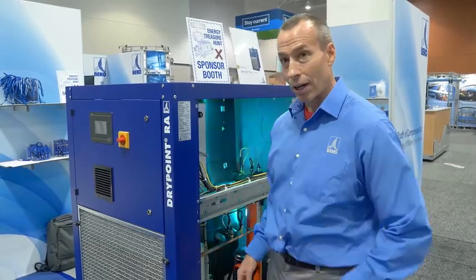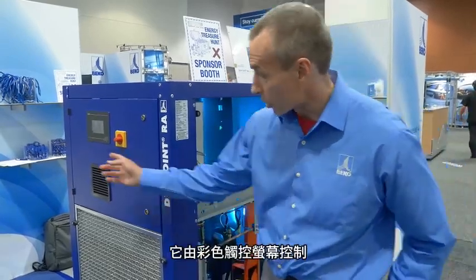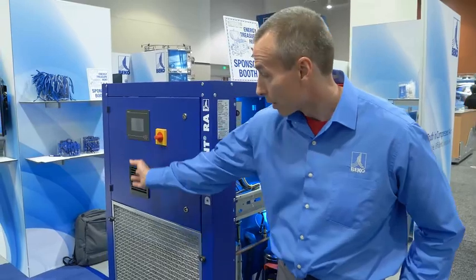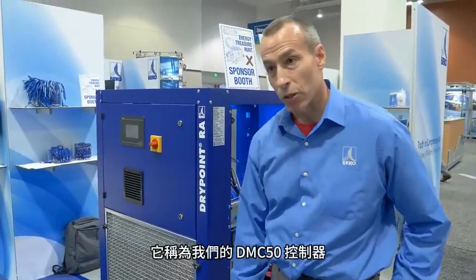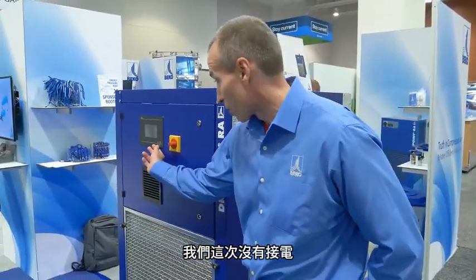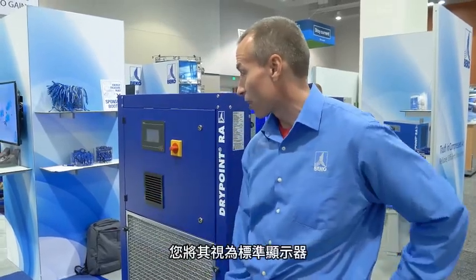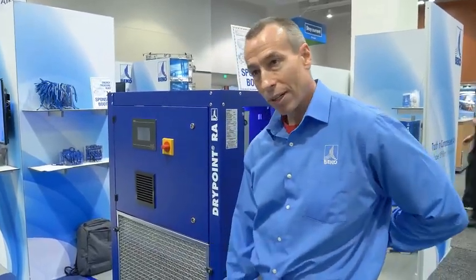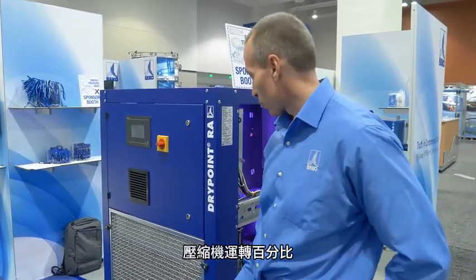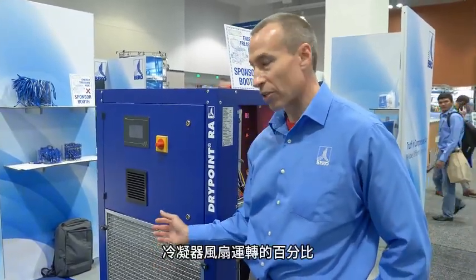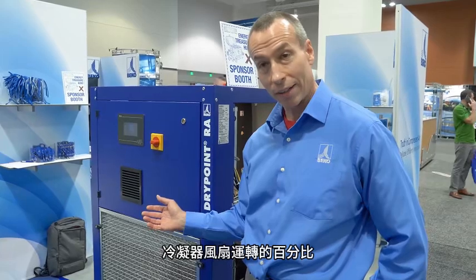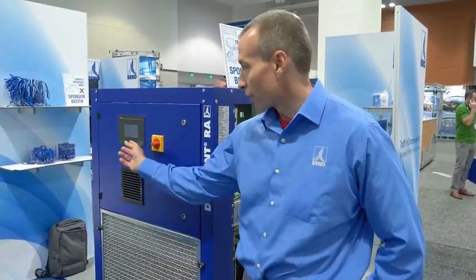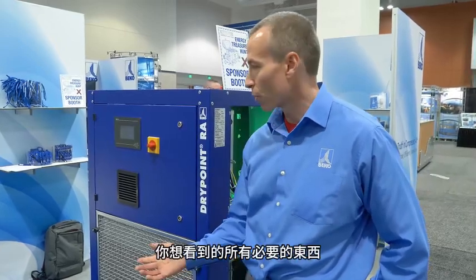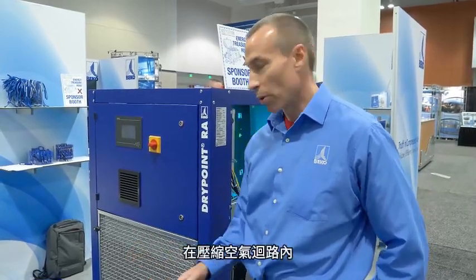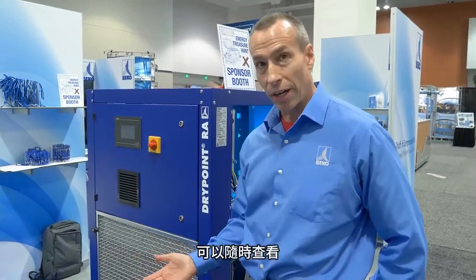It's controlled by a color touchscreen, which you can see right here. It's called our DMC50 controller. It's not active, unfortunately, but I can tell you that when it is activated, you see as a standard display, you'll see the dew point. You'll also see what percentage the compressor is running at, as well as what percentage the condenser fan is running at. You'll have features where you can get into the controller and you can look at all the variable parameters, all the necessary things you want to see, all the pressures and temperatures within the compressed air circuit. You can look at it at any time.